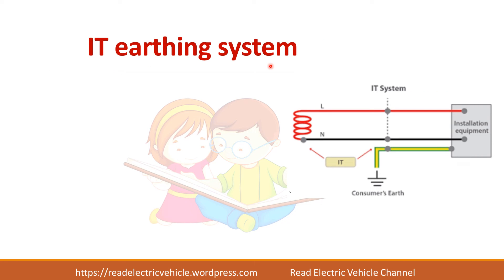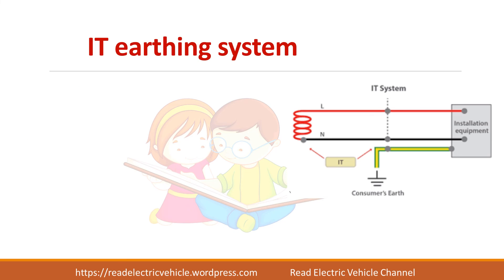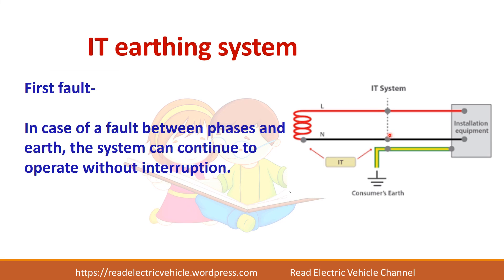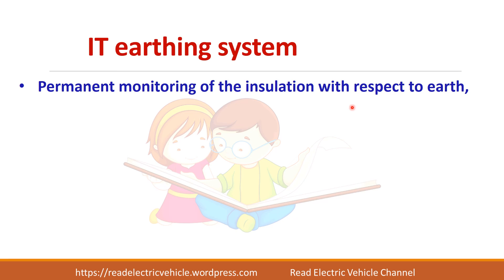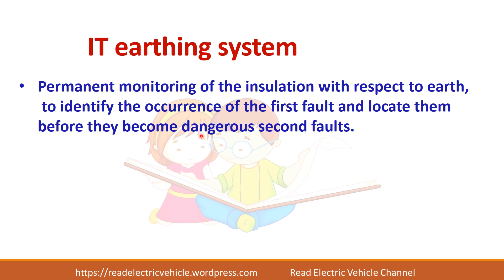In the IT earthing system, the first letter I means the live parts are isolated from earth — there is no connection to earth on the source side. The second letter T means the equipment is connected to earth. An important feature of the IT system is the first fault: when a fault occurs between the phase and earth, the system will continue to work without any interruption. However, this fault must be cleared immediately before a major second fault occurs. Permanent monitoring of insulation should be done so that any first fault is identified and cleared immediately.